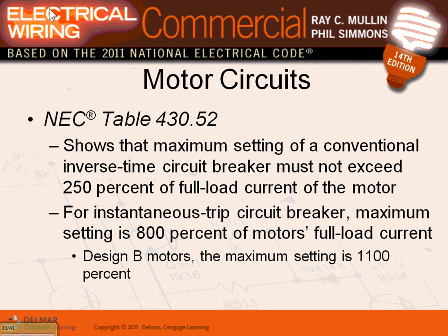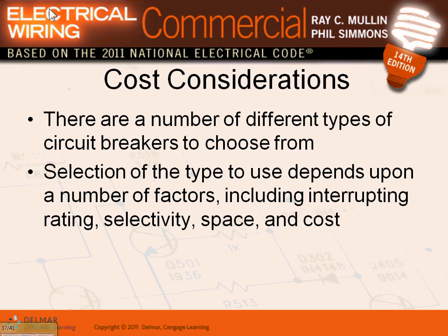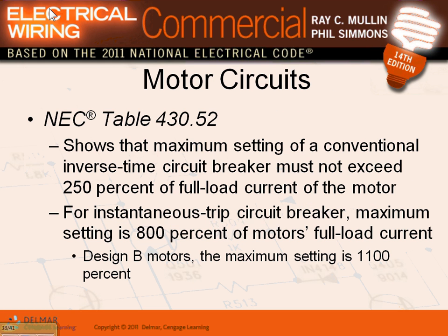Cost consideration. The whole idea of current limiting fuses and series rated equipment, guys, is to give you a reasonably priced project. You can have fully rated, but the problem is it's going to be very expensive, as you're going to see. So selection of type depends upon the interrupting rating, overcurrent coordination, the space, and the cost of the equipment. If the cost is not an issue, you can do anything you want.